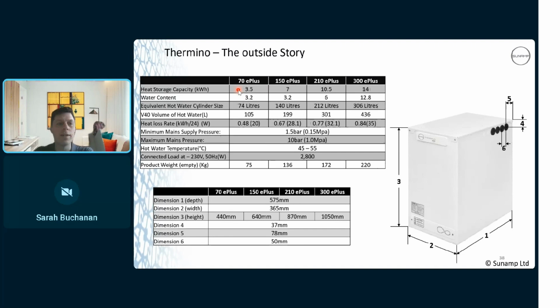So your heat loss calculation would be your storage capacity. If you want to make a note of these, we'll send these slides out to you, but this is a really good one for when you're speaking to your customers as well. Take your heat storage capacity, divide it by the heat loss, and that gives you your length of time in days before the battery is fully discharged.